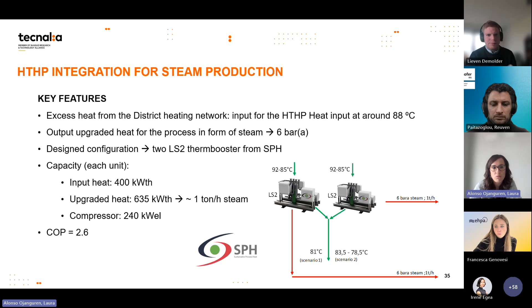So we have as input heat around 400 kilowatt thermal. The output heat is around 630 kilowatt. This corresponds to around 1 ton per hour of steam for each of the machines. And the compressor has an electrical power of 240 kilowatt. So with this source temperature and this sink temperature, the COP corresponds to around 2.6.